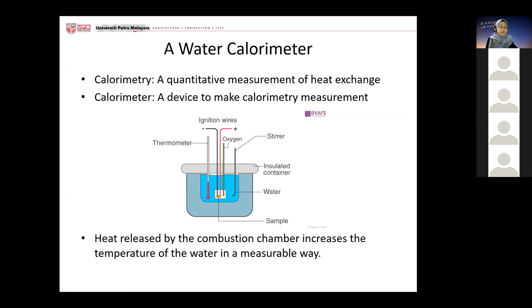Your sample here is usually in the form of a fuel, whatever fuel or material that you want to test, we can test it here. With the steel chamber, you want to do a complete combustion, which is why you need a very strong material for the combustion chamber. Whereas for the water calorimeter, if you try to Google, there are even some made from styrofoam. Styrofoam definitely cannot be used for a bomb calorimeter because you are burning the sample at a very high temperature, so you need a material that can withstand such high temperature and pressure. But the theory is similar.